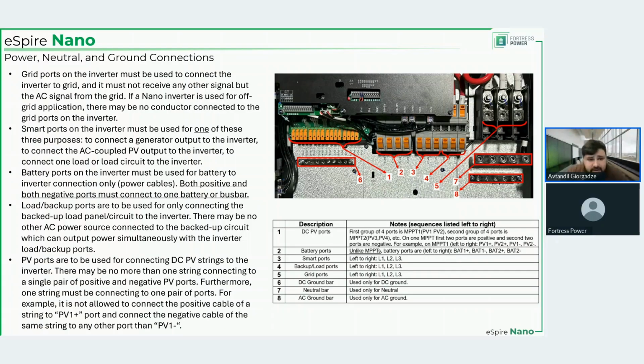Number 5 is where you connect the grid input, may that be whole site backup or partial site backup. The AC to the inverter is delivered through these 3 ports. That is number 5. And again, no generator on this side, no ATS with a generator on this side. Grid either directly from the meter or from a main panel board or some other sub panel must enter here. Only grid AC should be present at these ports. Although, to be honest, with pass-through, I would say most of the time you will not take the cables directly from the meter. But again, that could happen. You're more than welcome to do it. But remember, please, these ports are only for the grid.